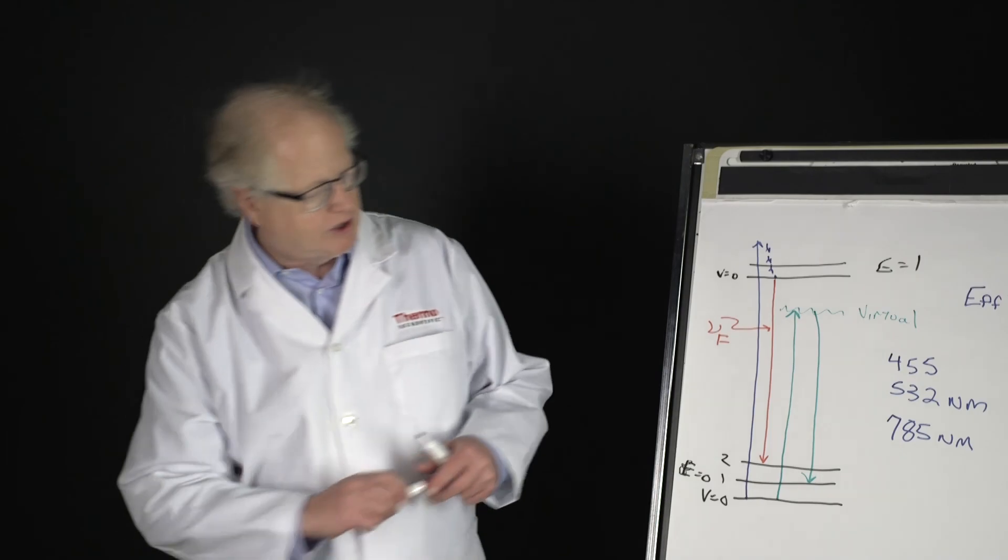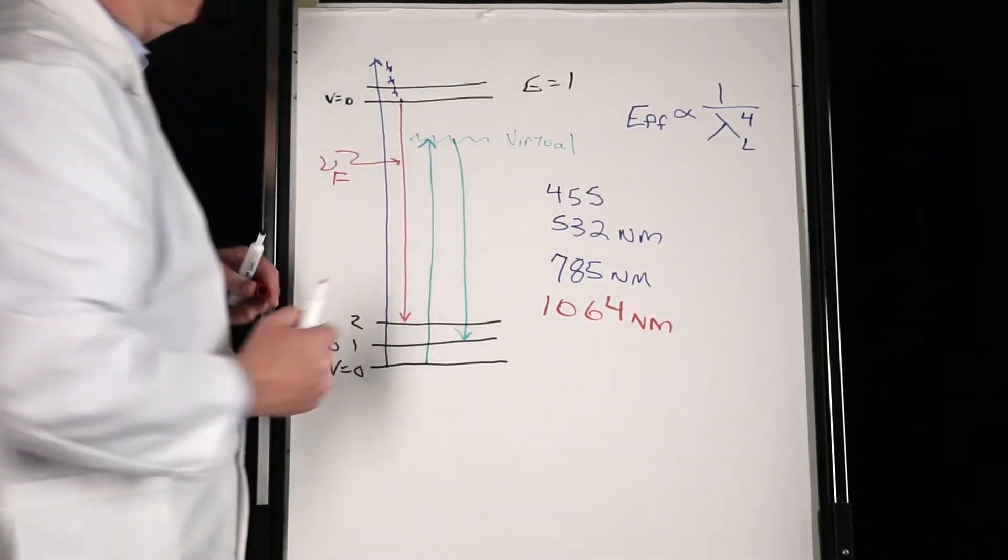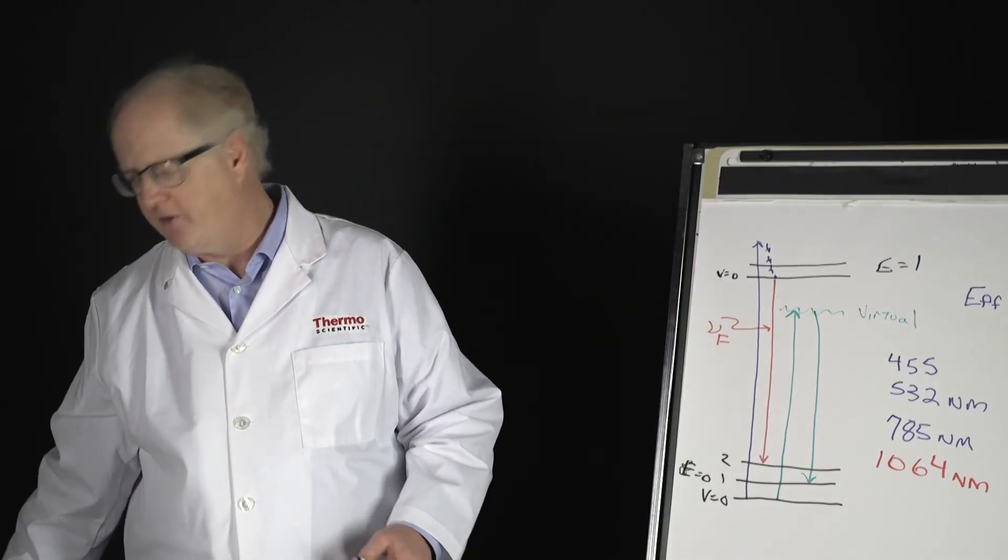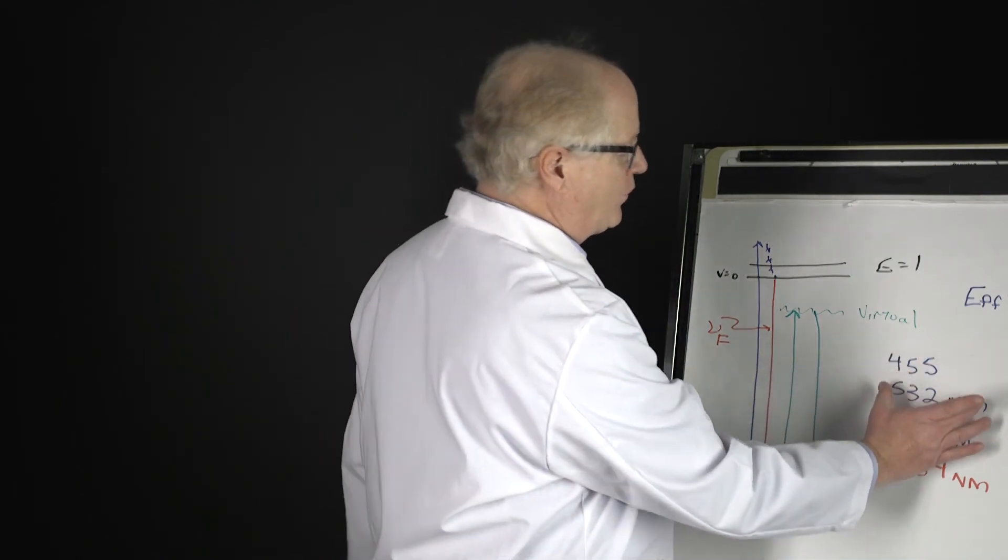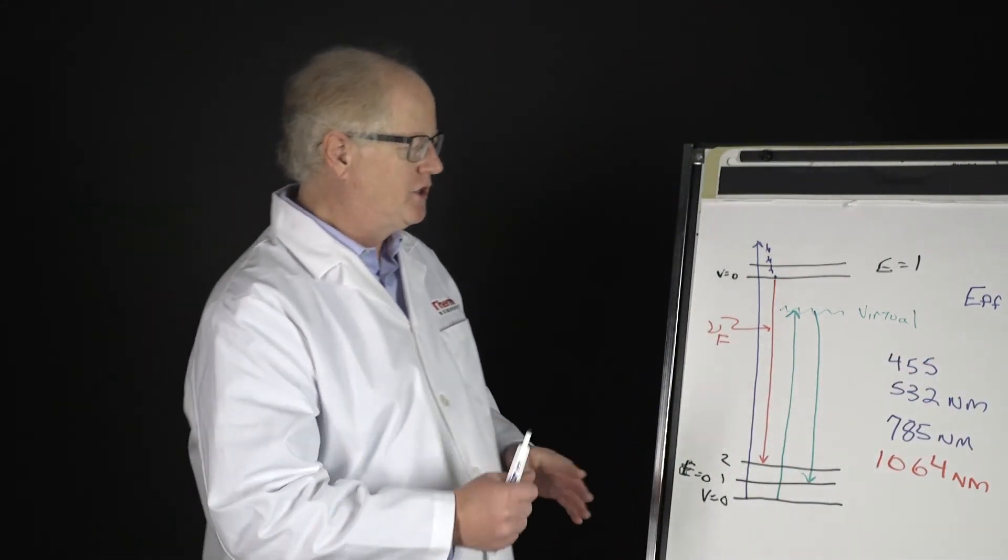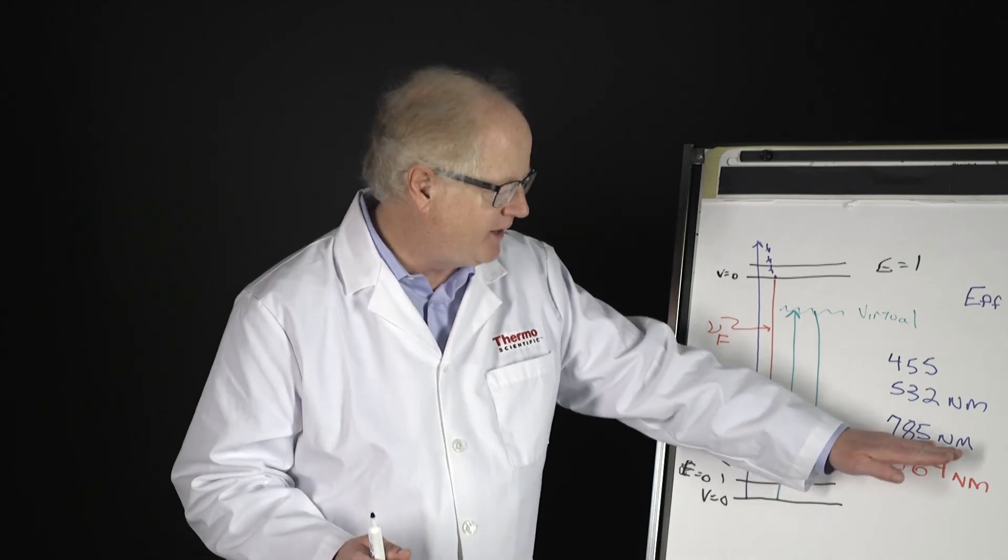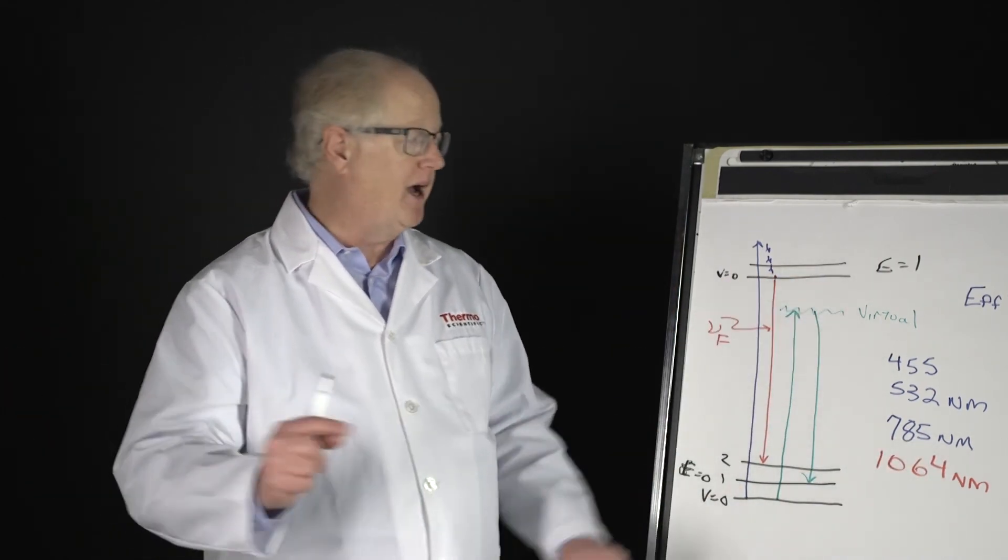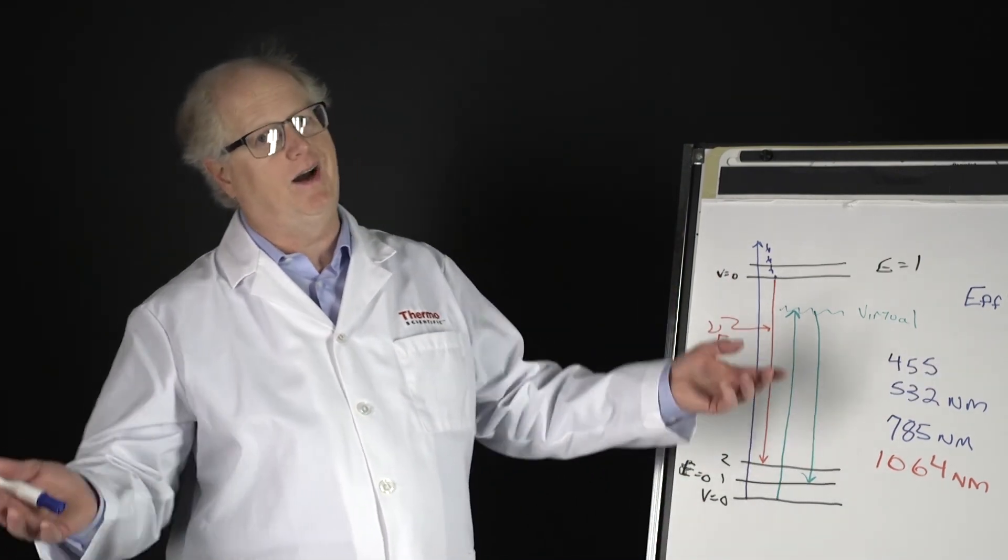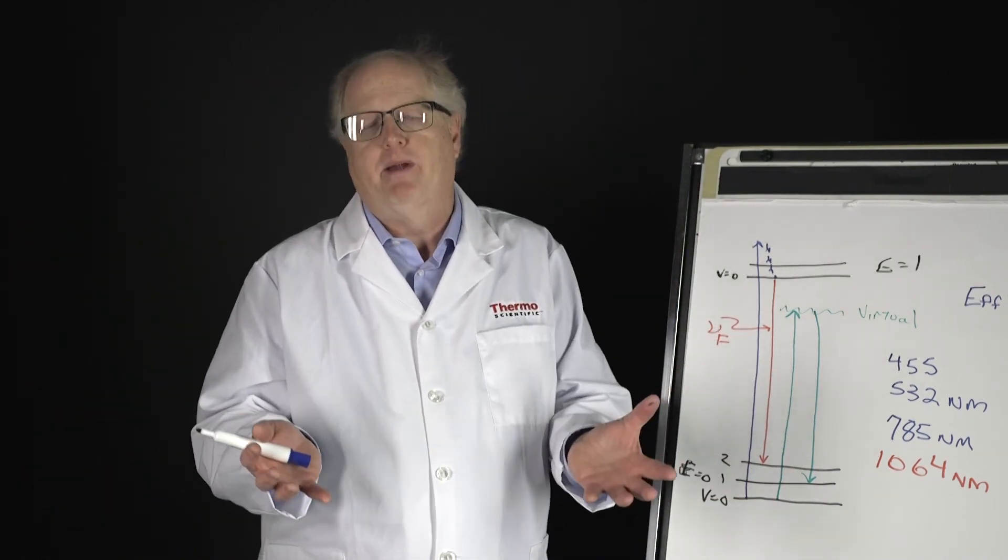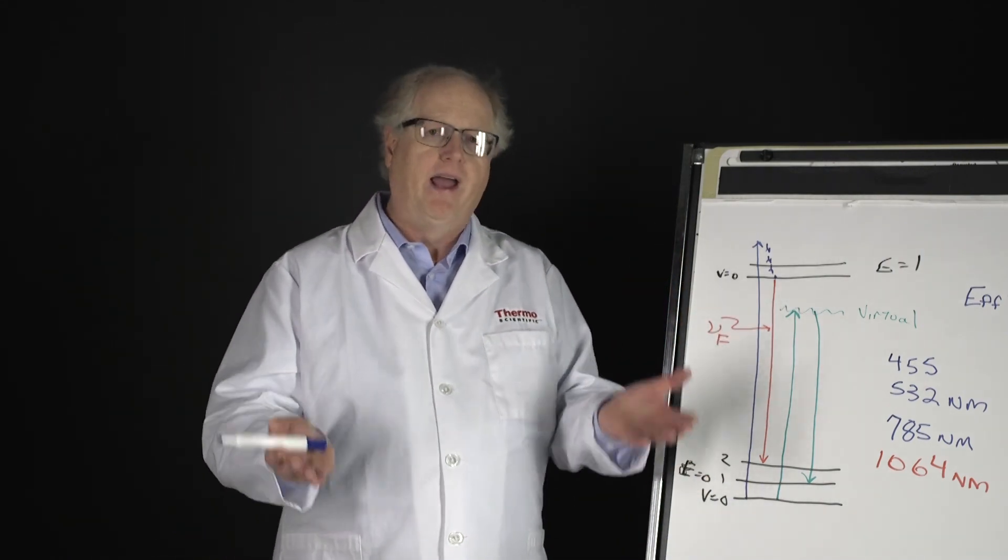It depends upon the molecule that you're looking at. Another laser that's used—and I'll explain why in just a few minutes when we look at FT Raman—is 1064. 1064 is ginormous; the efficiency is going to plummet. And there are times when you use a 1064 laser and don't see anything, use a 532 and you get these big peaks. So you see now there's the trade-off. This is why more than one laser is offered. You would think if avoiding fluorescence is all that mattered, use 785 or 1064—you're done. But the one over lambda to the fourth says you don't see anything. Oh, well then we need a shorter wavelength laser: 455. Ah, but the fluorescence will eat your lunch. There's a trade-off that has to be made, and this is why, as a vendor and as a user, you have to figure out how to balance these two—which lasers to buy.